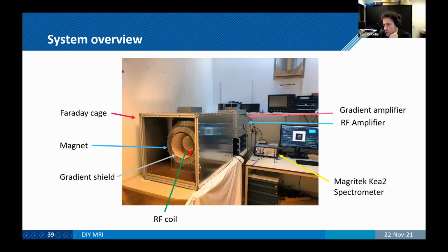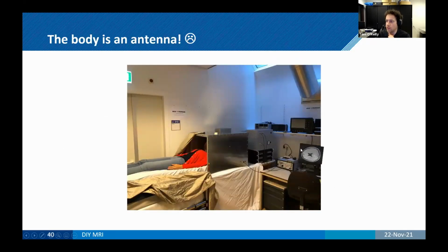So this is what the system looks like. We have the whole system placed inside of a Faraday cage: the magnet, the gradient shield, the RF coil, and then the amplifier directly behind it. When we're imaging, though, we do have an issue here: the body acts as a very good noise antenna. So if the body is sticking out of the Faraday cage, the noise will come in and completely destroy your image. It's about 50 to 100 times more noise.